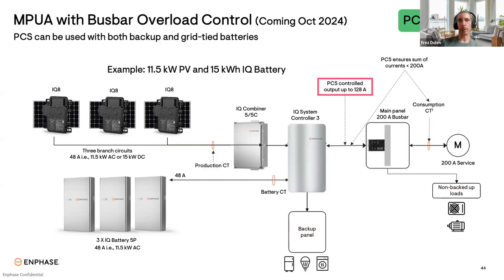Was it included also in the IQ Combiner 4? I assume that this is what they probably installed before. The Combiner 4 would not include the battery CT. Okay. So that would have to be purchased separately. A battery CT isn't required for just a regular battery backup system without using PCS. But if PCS is being used, then, and now that I say that out loud, I think I'm getting that wrong. Forgive me for a moment there for that slip up. The battery CT is going to always be required with any battery system.